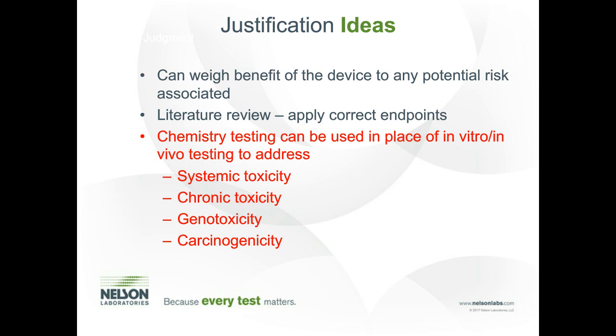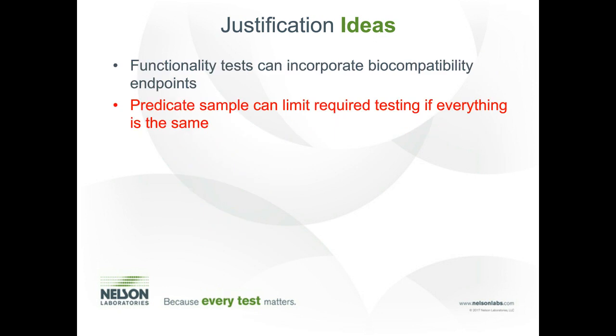And this is kind of what I talked about before. First off, functionality testing. Most medical device manufacturers perform some type of in vivo functionality tests before we look at biocompatibility, trying to get the design down right. I really want to recommend that you work with your CRO. If you are performing your functionality test outside of your normal CRO, at least contact your CRO about implementing biocompatibility endpoints in those functionality tests.